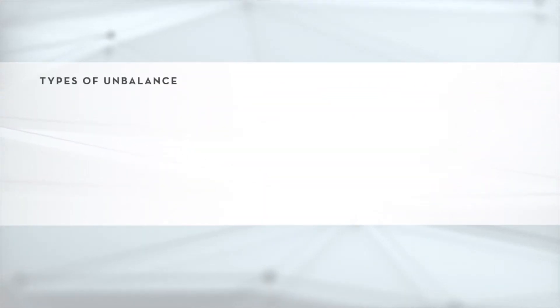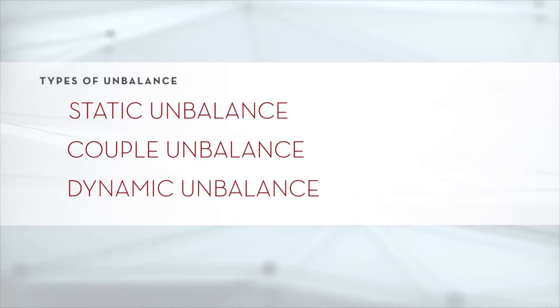There are three types of unbalance: static unbalance, couple unbalance, and dynamic unbalance.